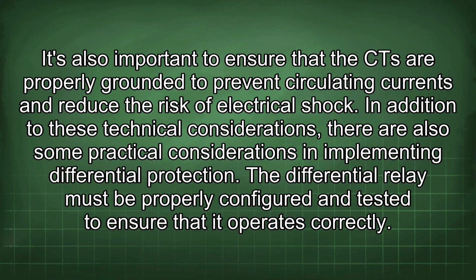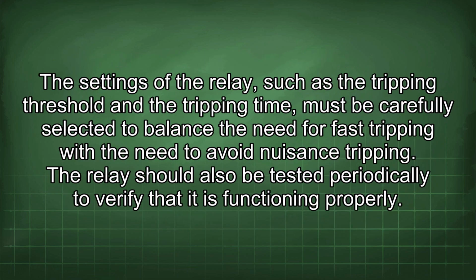The differential relay must be properly configured and tested to ensure that it operates correctly. The settings of the relay, such as the tripping threshold and the tripping time, must be carefully selected to balance the need for fast tripping with the need to avoid nuisance tripping. The relay should also be tested periodically to verify that it is functioning properly.